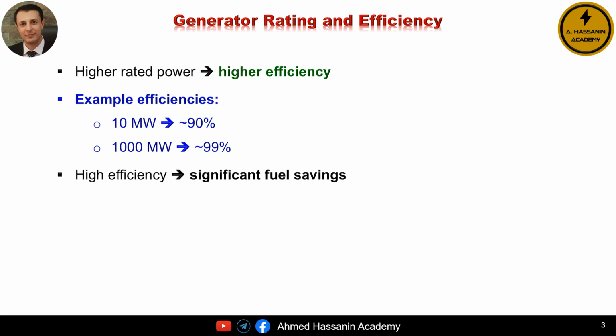Now let's talk about generator rating and efficiency, because this is one of the most important ideas in large-scale power generation. In general, the higher the rated power of a synchronous generator, the higher its efficiency. Small generators lose a noticeable portion of their input energy, but as we move to larger machines, those losses become relatively smaller compared to the output power.